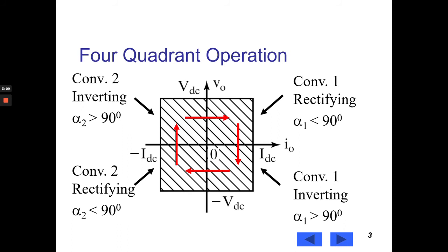The direction of rotation reverses. This converter acts as an inverter for alpha greater than 90 degrees. The average load voltage is positive but the average load current continues to be negative. Therefore, the power flow will take place from load to source. The load acts like source, that is the motor will act as a generator and regenerative braking will take place.